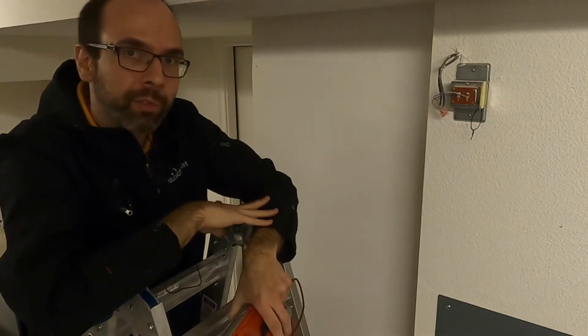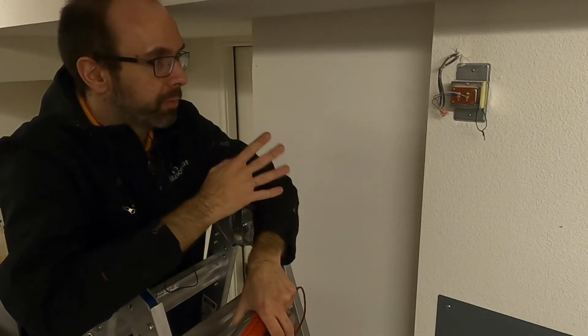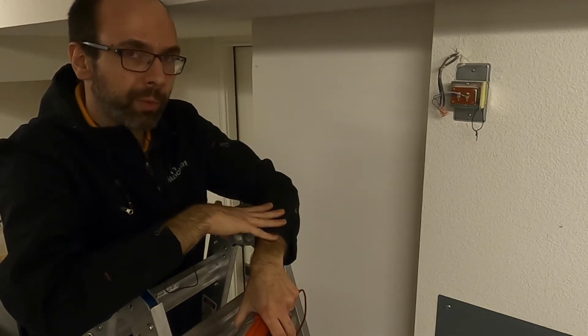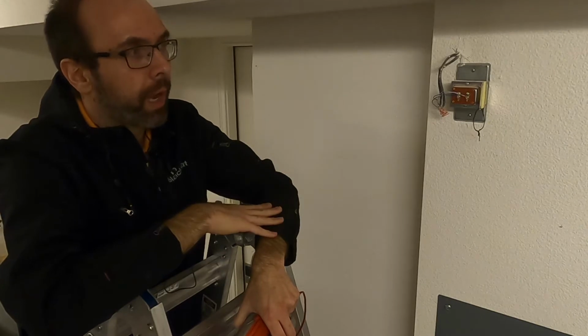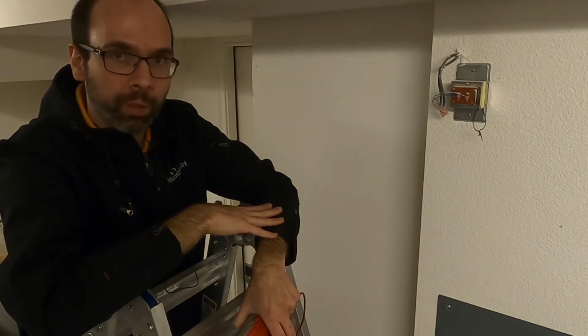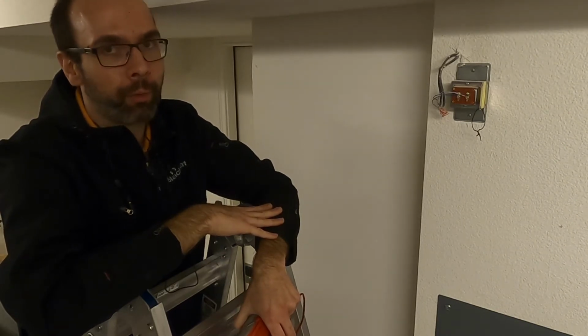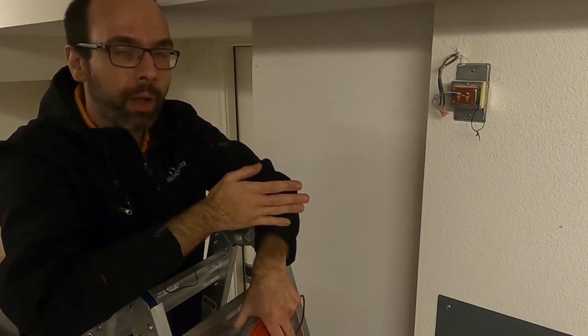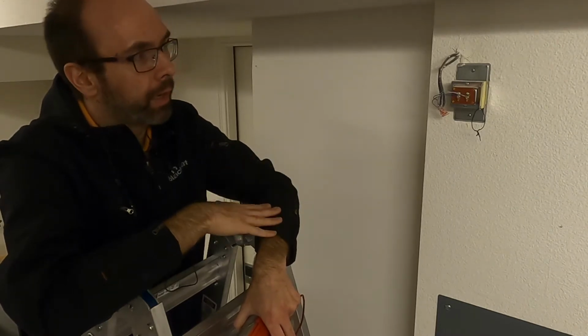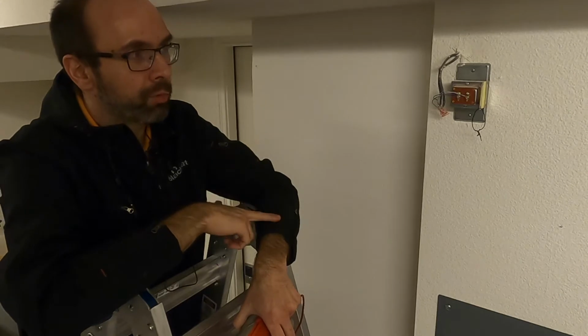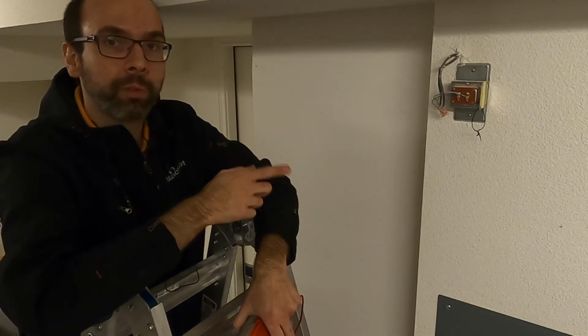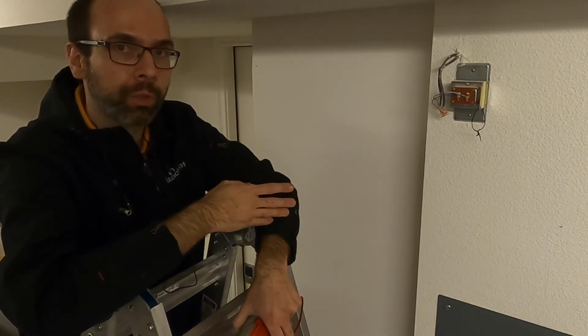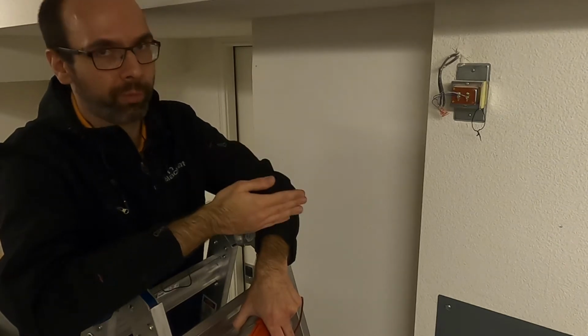The next step is to see if we can find some specifications about that transformer. Specifically, we need to make sure it has enough power available to supply the Wyze camera. The Wyze camera uses 5 watts maximum as per its labeling, and I have to make sure this transformer has enough capacity to supply not only the existing loads, which I have to measure, but also the Wyze camera on top of everything else.